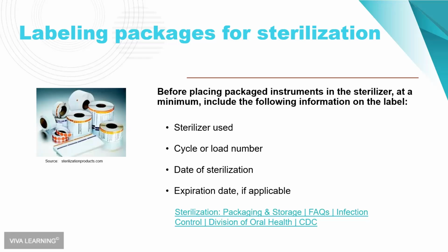But what the CDC says in their guidelines for packaging and storage is that you should label each package with the sterilizer that was used, so you can number them, or you can put the name of the sterilizer. You label it with the cycle number or the load number, whatever you decide, and the date. You could put an expiration date, but it's really not applicable for what we use in our dental practices. So: which sterilizer was used, what was the load number, and what was the date of sterilization. So if you have a failure on your spore test, you know which packages, not yet reused, had been processed in that particular load.